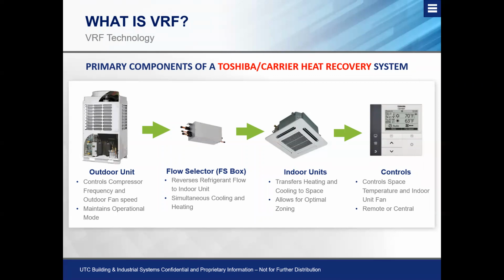Okay. Now on our flow selector boxes, since we have three pipes feeding into it, we don't need a gas liquid separator like we did on the carrier system. So these boxes are made up of two main components: solenoid valves that open or close depending on what indoor unit is calling for what, whether it be cooling or heating. And we also have a tube-in-tube heat exchanger, which again, just like in the carrier system, subcools that liquid refrigerant so that we can get greater heating distances from this box.